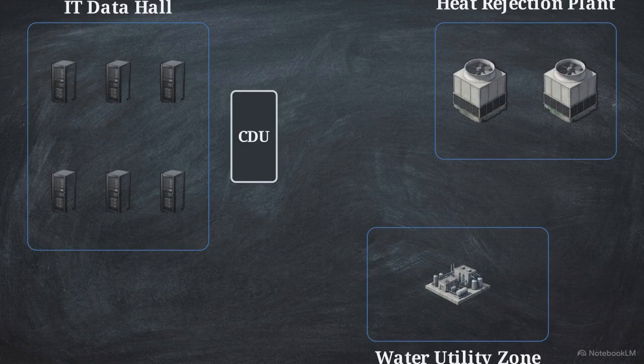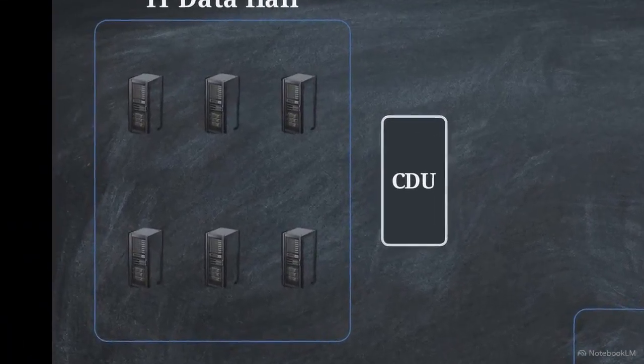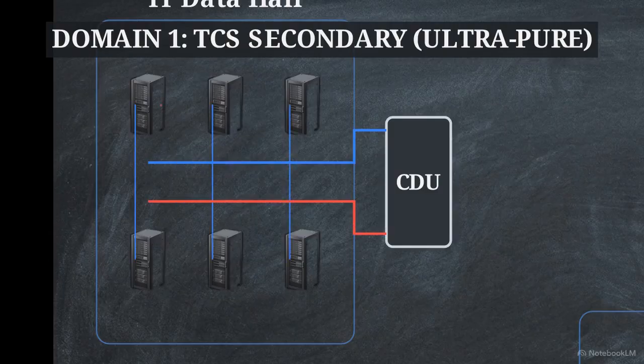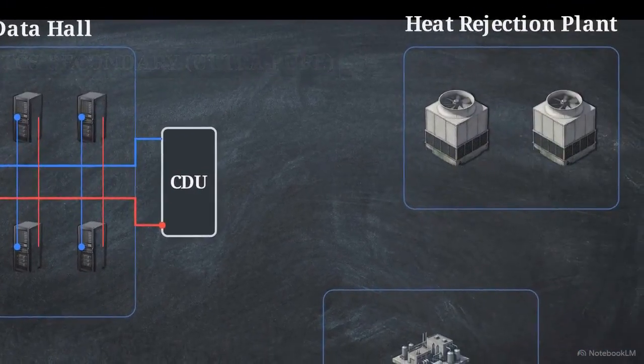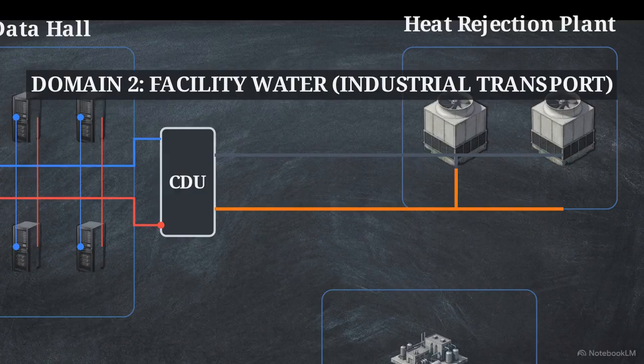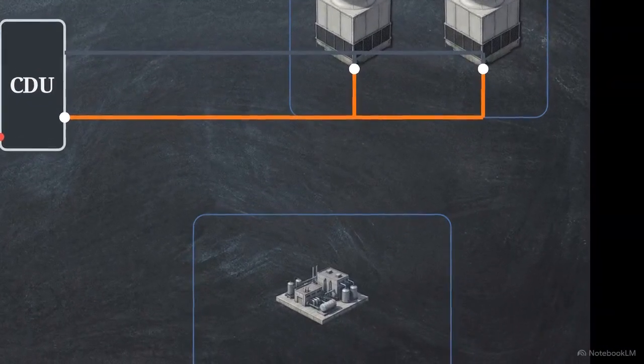The campus must maintain 3 independent, rigorously separated fluid domains. Maintaining absolute isolation between these loops is a non-negotiable design requirement. Domain 1 is the Technology Cooling System, or TCS, secondary loop. This circulates through the data hall. It is an ultra-pure, chemically inhibited, and degassed coolant, engineered to meet server OEM specifications. Domain 2 is the primary facility water loop. This heavy-duty industrial piping network provides bulk thermal transport, carrying the thermal load away from the IT equipment and out to the heat rejection plant.